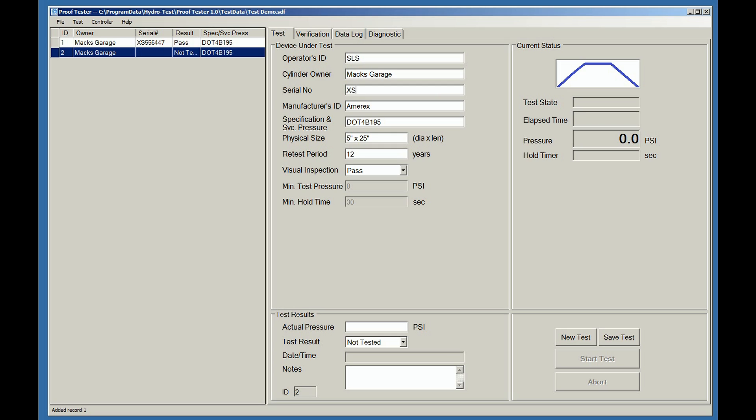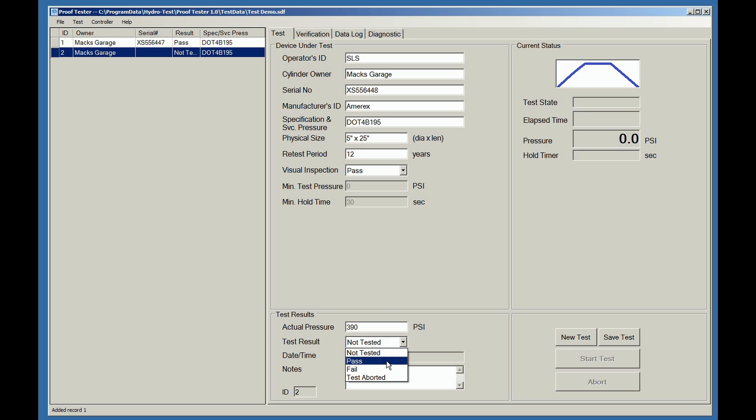So in this case, we'll type in a new serial number for this particular cylinder. And all of the other information is the same. And we'll put in a test pressure. And this time we went exactly to 390 PSI. It passed the test again.